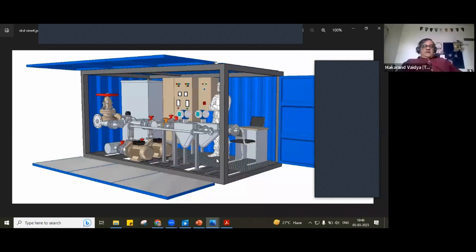Yeah, actually, it has been calculated by that flow computer. That was what I was about to tell. That software has all the uncertainty, accuracy, repeatability, statistical analysis and all that. It is a kind of semi-automatic thing. Once you put it under calibration test, it automatically captures the data and makes an Excel sheet or chart form, ready for you to accept or reject.